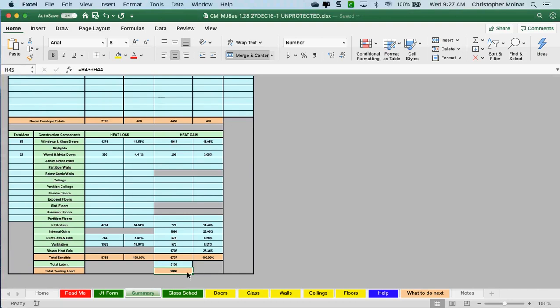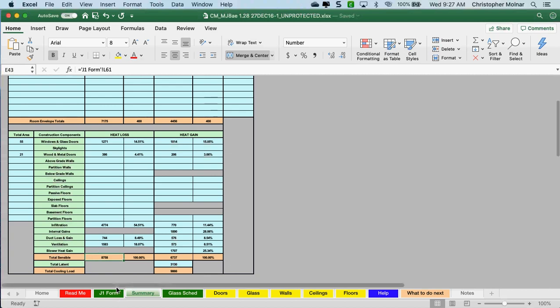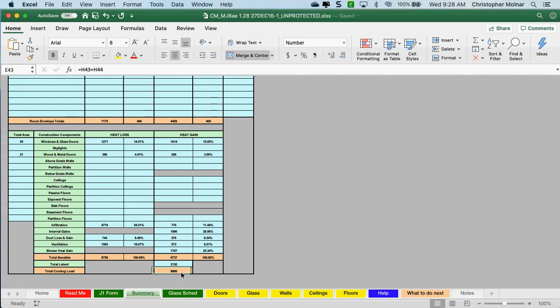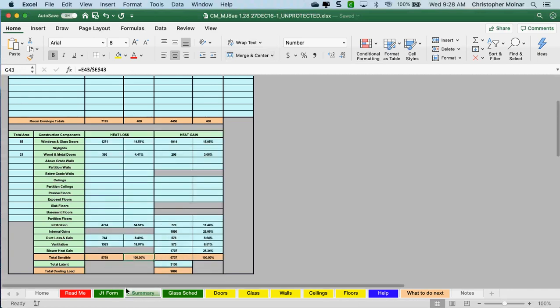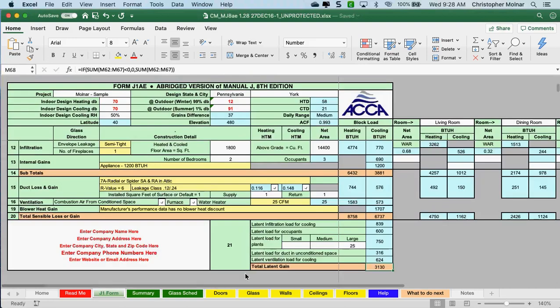The last line is the BTUs of your air conditioning — divide by 12,000 BTUs and that tells you how many tons of cooling you need. Sensible heat under heat loss is the size of the output of the furnace or whatever heating system you use. Part five is wrapping this up — giving me this summary page. Everything is complete for this spreadsheet.